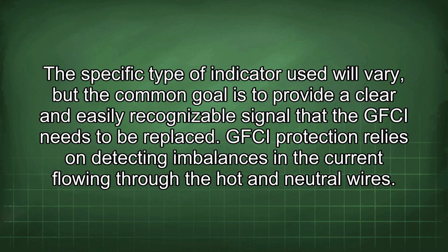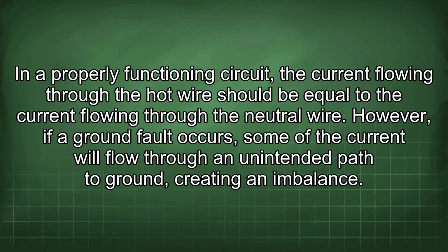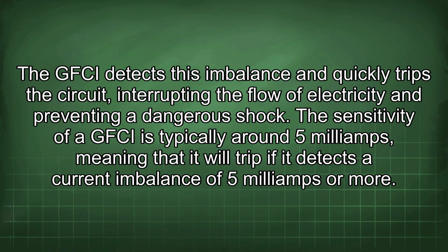GFCI protection relies on detecting imbalances in the current flowing through the hot and neutral wires. In a properly functioning circuit, the current flowing through the hot wire should be equal to the current flowing through the neutral wire. However, if a ground fault occurs, some of the current will flow through an unintended path to ground, creating an imbalance. The GFCI detects this imbalance and quickly trips the circuit, interrupting the flow of electricity and preventing a dangerous shock. The sensitivity of a GFCI is typically around 5 mA, meaning that it will trip if it detects a current imbalance of 5 mA or more.